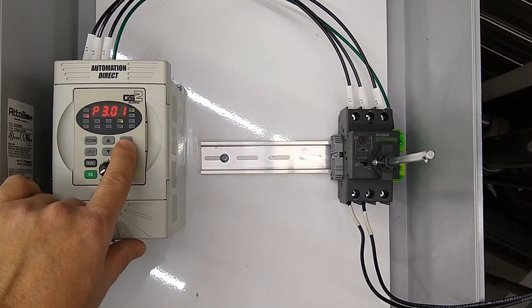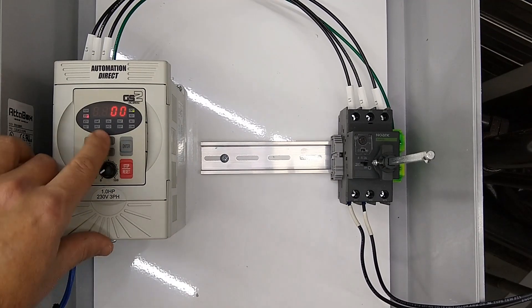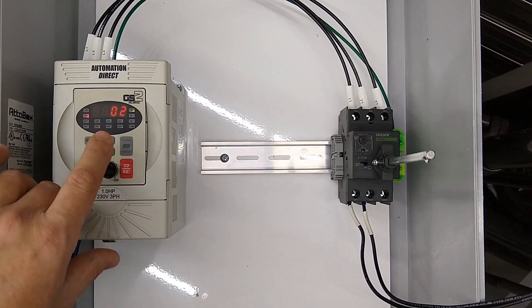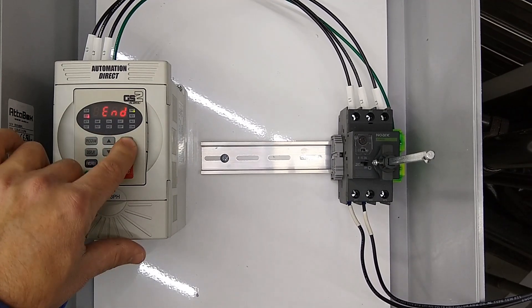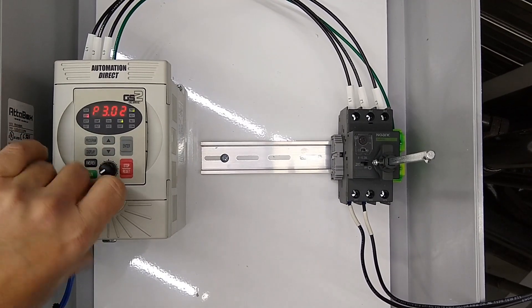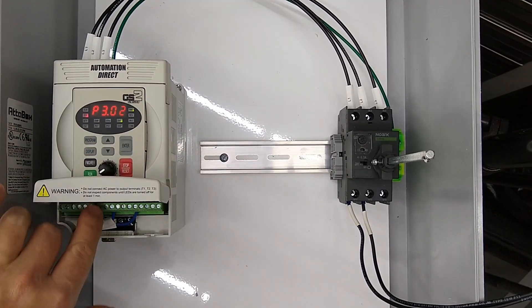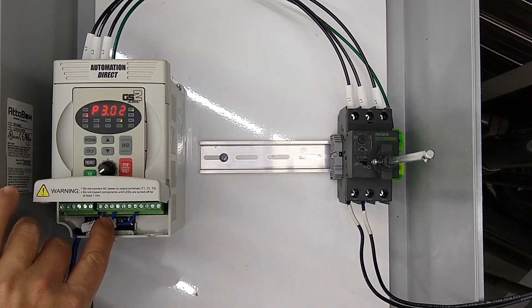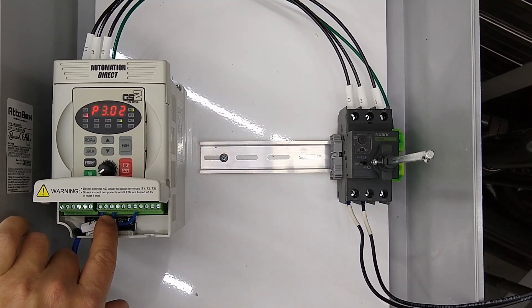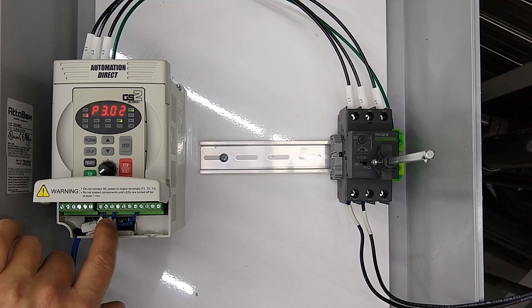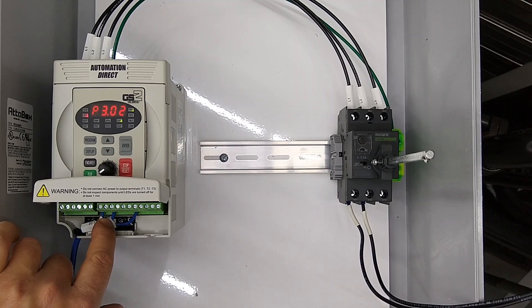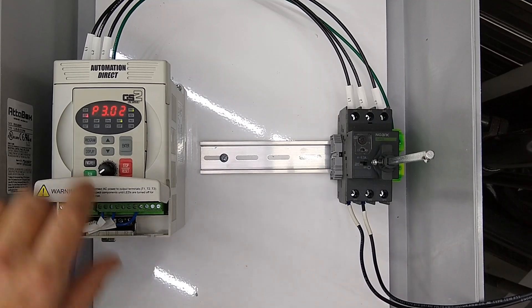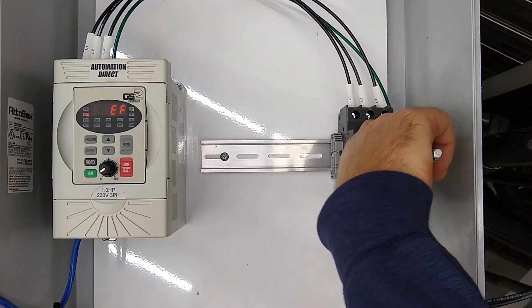Then we're going to change p3.01 to a 2, which is going to make DI1 our start terminal. DI2 actually can be used to reverse the motor—we're not using that on this one—and then DI3 is our stop terminal.